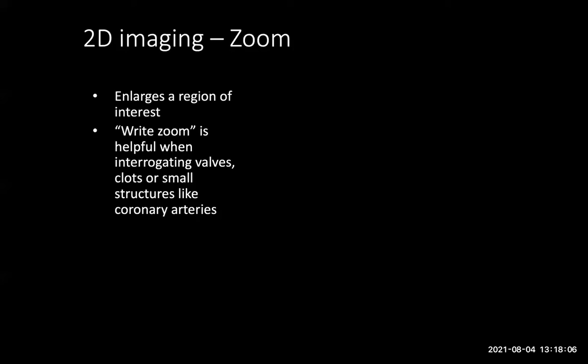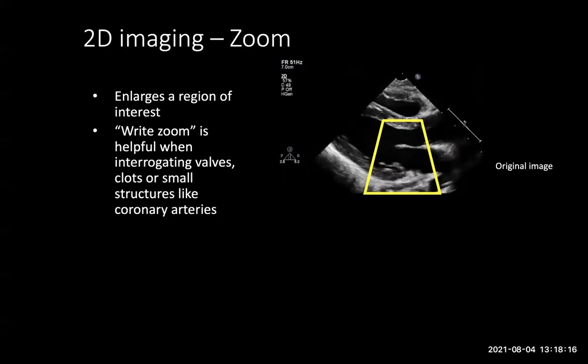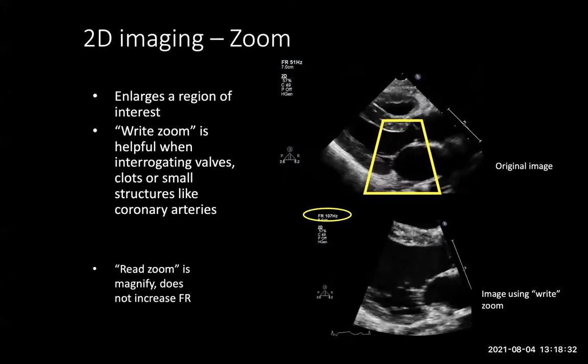The last technique I want to mention about 2D images is zooming. As it implies, it enlarges an area of interest and is helpful when assessing valves, clots, or other small structures. So we have our larger image of the parasternal long axis, but we want to investigate the mitral valve in more detail. Using our write zoom, we can select the area of interest and activate it. Since this method only scans the selected section, you get better resolution and the added bonus of a higher frame rate. Now, this is different from read zoom, which simply magnifies your original image, so you will not gain a higher frame rate or better resolution.